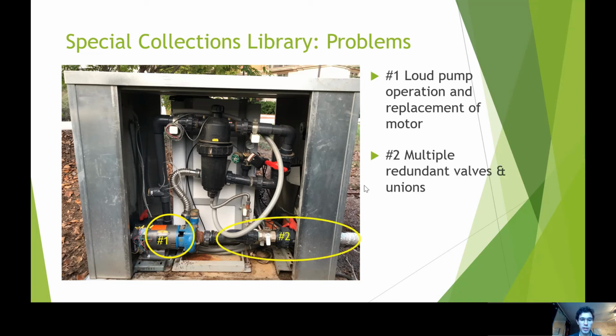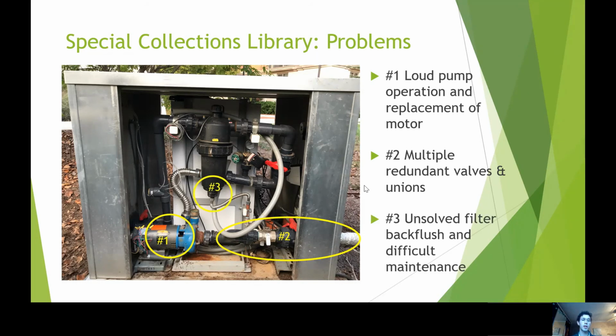In addition, there are multiple redundant valves and unions leading from the tanks to the pump. Each of these points is a possible entrance point for additional air to cause additional damage through cavitation. So this is a problem. There's also an unsolved filter backflush system that never worked, and the filter there is very difficult to maintain. It's extremely difficult to unscrew and take off and put back on because of its unwieldy position. It's too close to the back panel there to be really easily maneuvered.